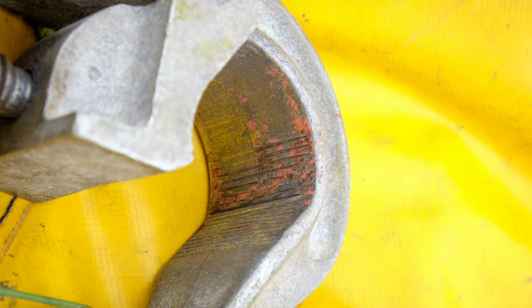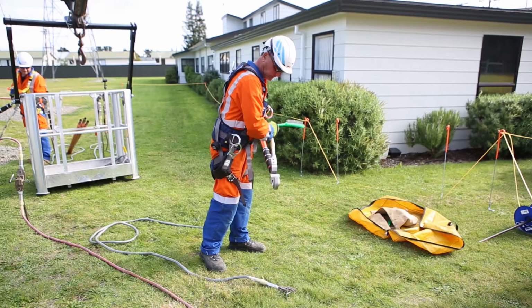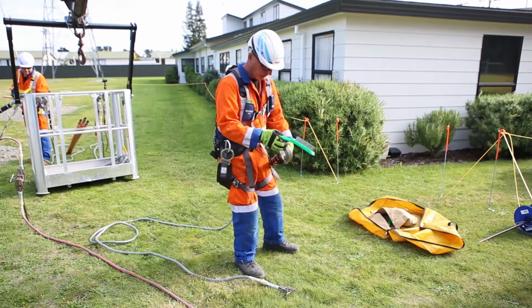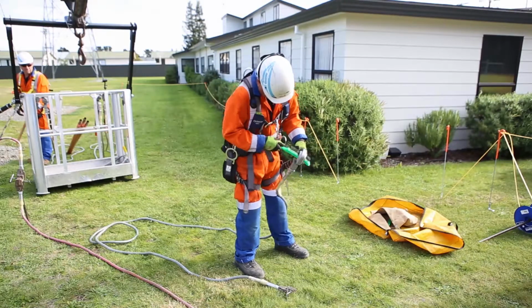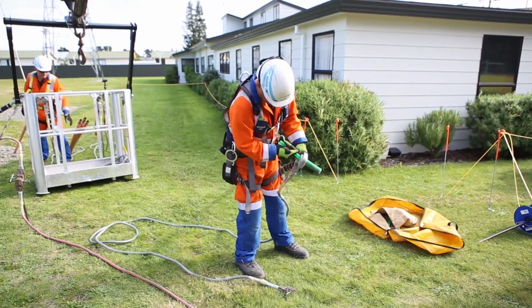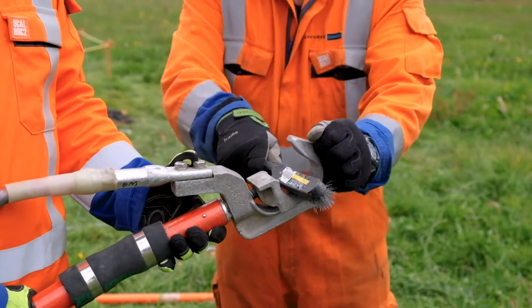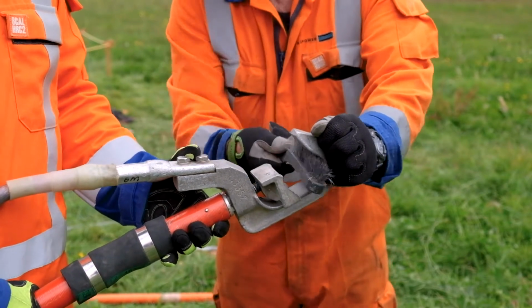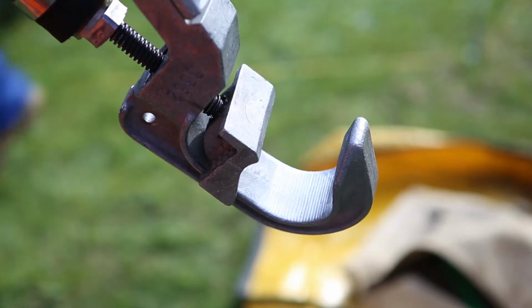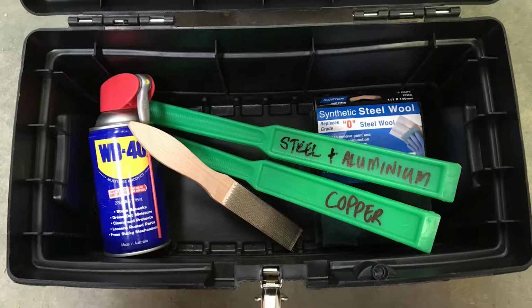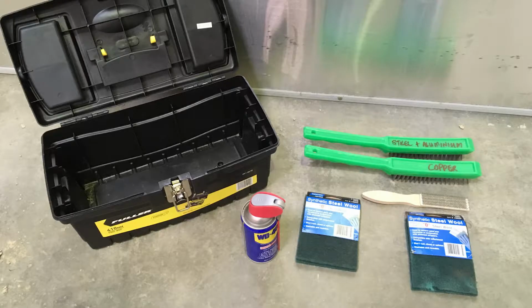Of course, cleaning your head clamp is just as important as the tail clamp. Remember that the head clamp is designed as a fixed hook, and that the moving jaw is just for clamping it to the conductor. Use a stainless steel wire brush to clean the inside surface of the hook end, which will be clamped onto the conductor. You should keep a wire brush just for cleaning aluminium. If it is used to clean other metals, especially copper, as well, it can cause cross-contamination corrosion issues.